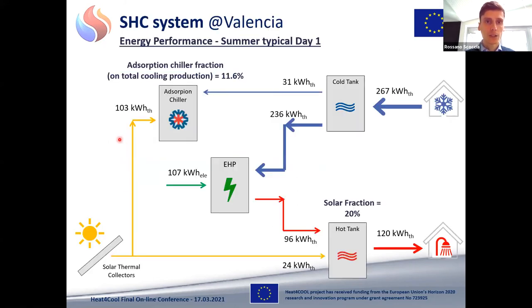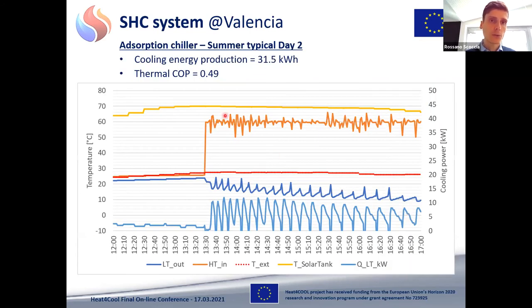Here I show you how the system in Valencia works for a typical day. And this energy is used also for the production of domestic hot water. We managed to achieve on this day a solar fraction of 20% in order to produce 120 kilowatt hours of thermal energy in the end. Now I will show you a focus on the adsorption chiller for another typical day. On this day, we produce 31.5 kilowatt hours of cooling energy with a good thermal COP for this kind of machine, 0.5.